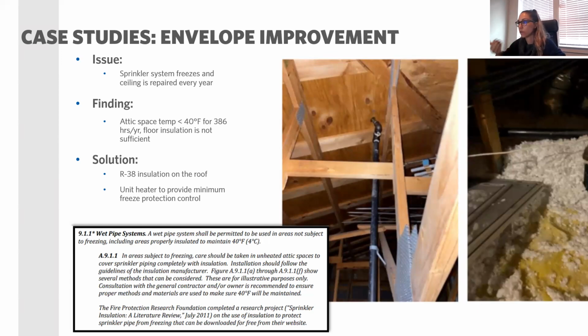So then we did a quick calculation, and we saw the space temperature actually gets below 40 degrees for 386 hours per year, because the floor insulation was not helping the heat. So our recommendation, and this is also another code violation, because the plumbing or fire code requires that if you have a wet system, the space has to maintain a 40-degree temperature.